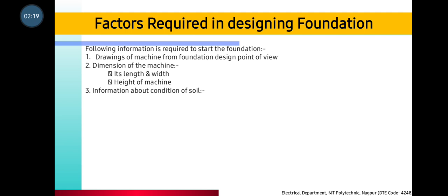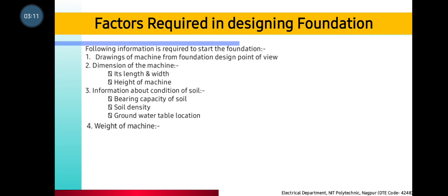Information about condition of soil — soil condition, bearing capacity of soil — because you can use the material for the foundation to build, and where you can build the foundation. It will be soil on the top, then cement, then foundation block, then the motor on top. So you have to see the soil bearing capacity, soil density, how deep it is, and the ground water table location.